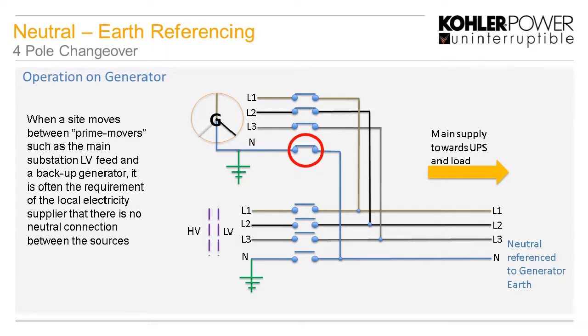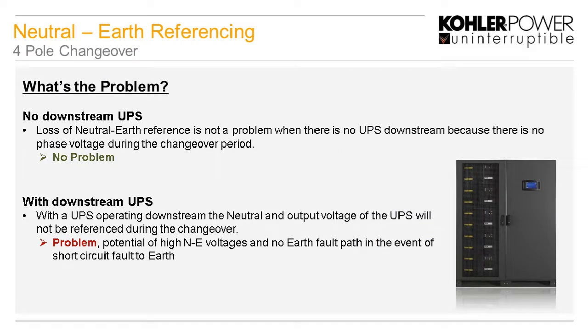Okay, so what's the problem here? Now, if we don't have a UPS downstream, when we have a changeover, we lose the neutral earth reference, but there's no UPS, there's no output voltage during that period, so it's not a problem. However, if we do have a UPS in circuit, the UPS continues to operate when the mains has failed or when both breakers are open on the changeover. And the output of the UPS is still outputting 240 volts line to neutral, but that neutral now is floating and is no longer referenced to the earth, as we've seen in the previous diagram.